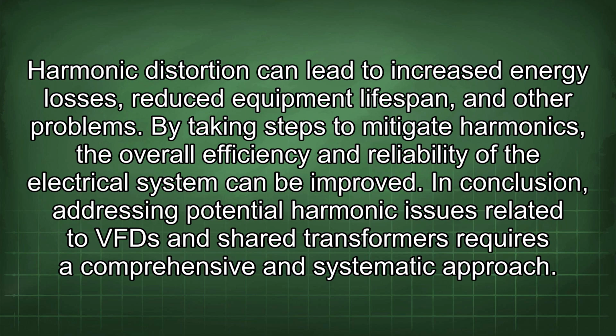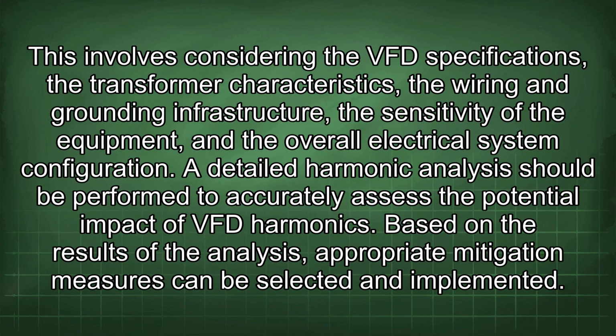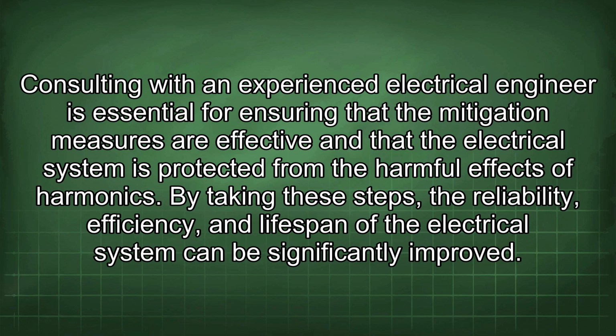In conclusion, addressing potential harmonic issues related to VFD and shared transformers requires a comprehensive and systematic approach. This involves considering the VFD specifications, the transformer characteristics, the wiring and grounding infrastructure, the sensitivity of the equipment, and the overall electrical system configuration. A detailed harmonic analysis should be performed to accurately assess the potential impact of VFD harmonics. Based on the results of the analysis, appropriate mitigation measures can be selected and implemented. Consulting with an experienced electrical engineer is essential for ensuring that the mitigation measures are effective and that the electrical system is protected from the harmful effects of harmonics. By taking these steps, the reliability, efficiency, and lifespan of the electrical system can be significantly improved.